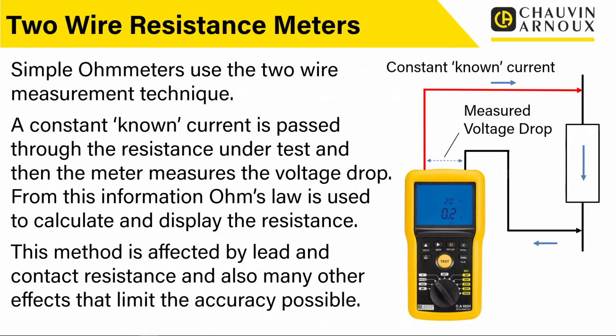So we've got various options for low resistance measurement, and in many cases we may just use a simple 2-wire resistance measurement. So simple ohm meters use the 2-wire measurement technique. In this, a constant or known current is passed through the resistance under test, and then the meter measures the voltage drop between its terminals. From this information, Ohm's law is used to calculate and display the resistance.